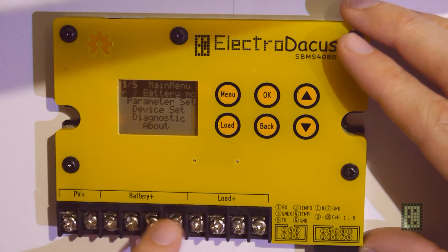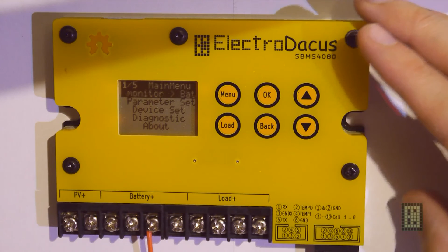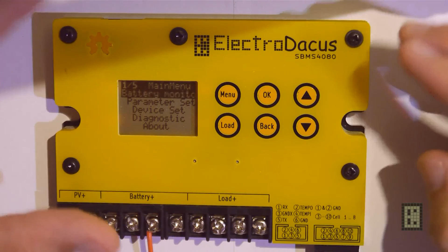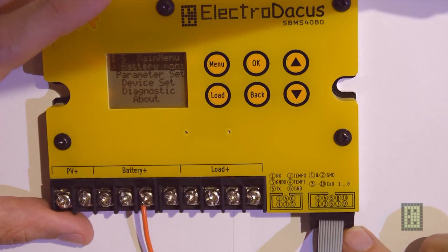When you first get this, you need to connect the battery first. That's the first thing you need to connect, the battery cable, the positive one. The ground connections from battery, PV panel and load are all connected outside the Solar BMS together, and the Solar BMS will interrupt the positive lead. So you first just connect the battery, nothing more, and then you insert this 10 pin sensor connector that measures individual cell voltages, but also powers the Solar BMS.